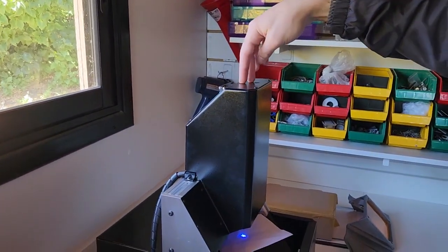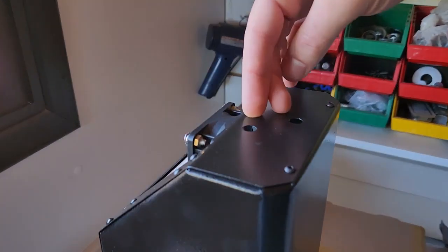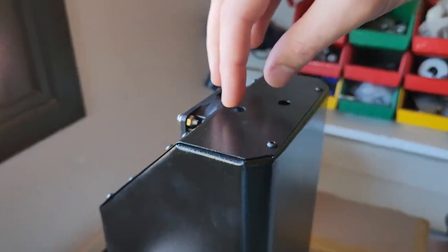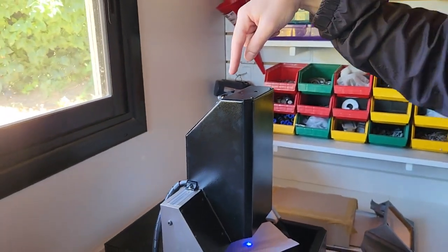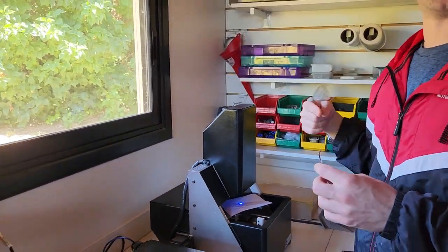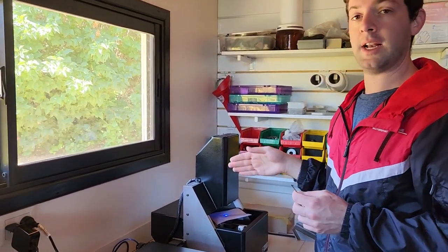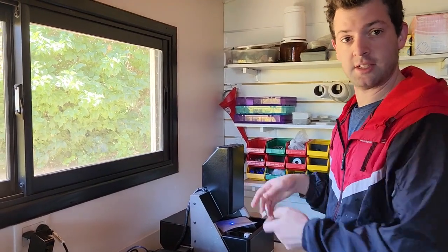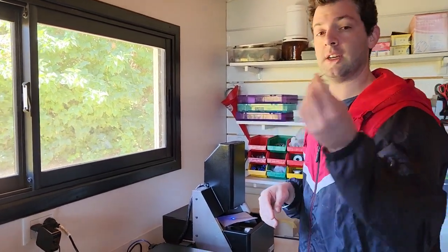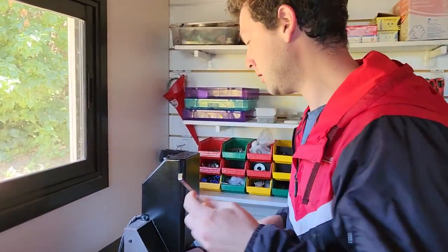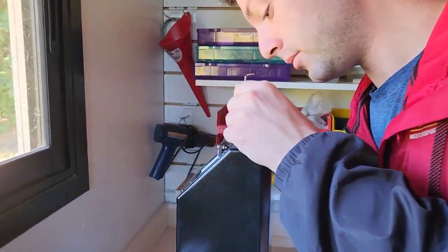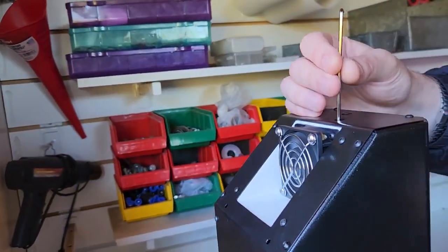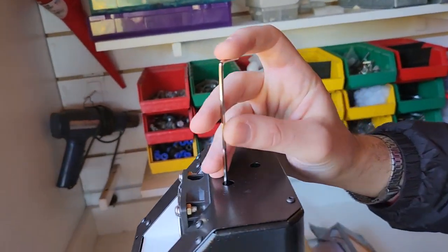We have two holes here in the top of the cover, and these holes correspond with two screws for rotating the tilt of the laser inside the machine. What we need to do is align it with a pinhole that's inside the optics. For this we need a 2.5mm Allen key, and we just put it through the holes. And we need to check here on the laser.